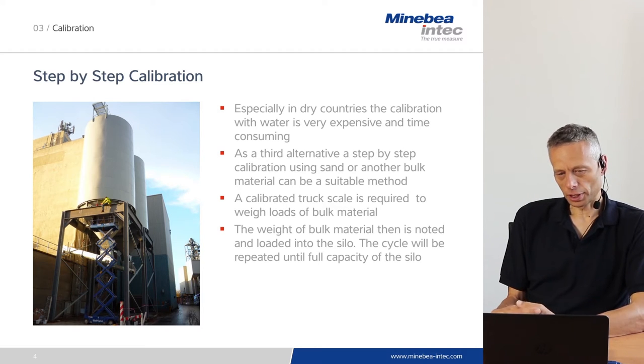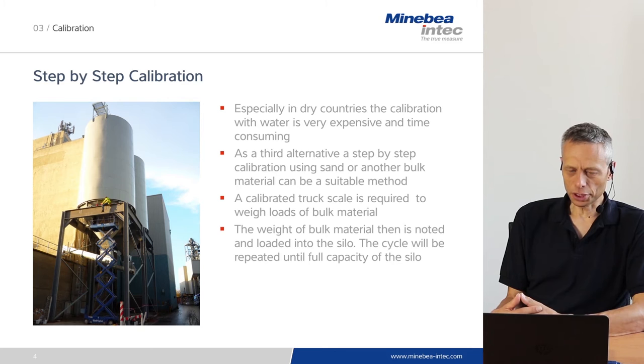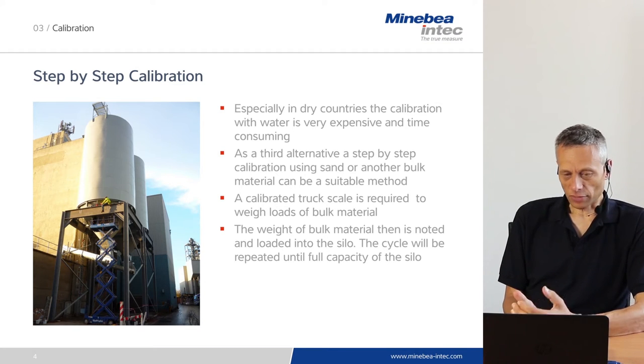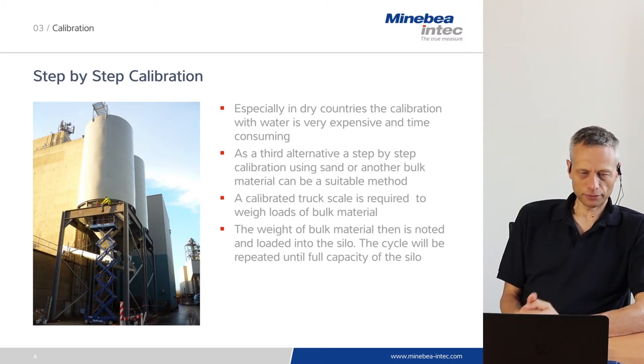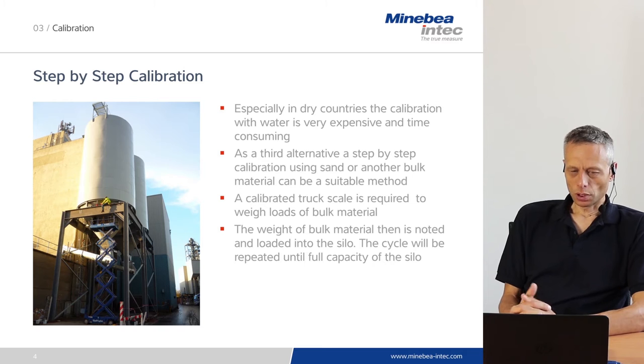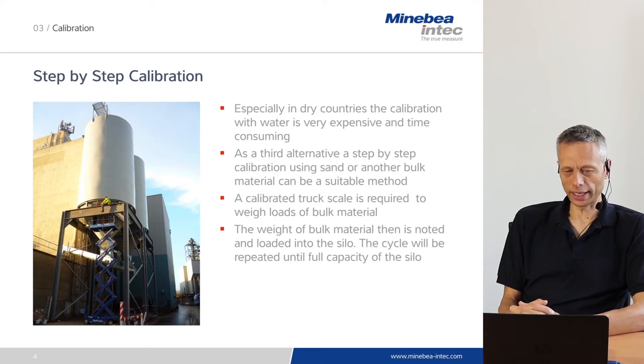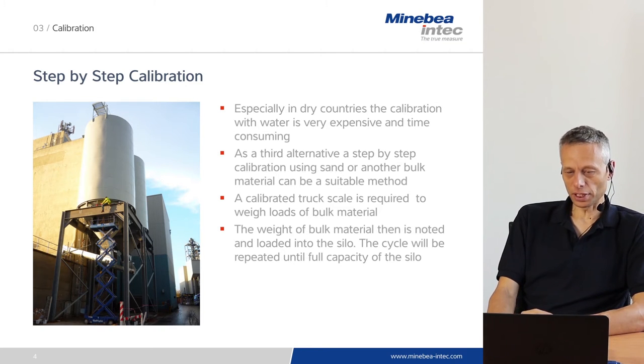Another possibility is the so-called step-by-step calibration. Especially in dry countries, calibration with water is very expensive and time consuming. Step-by-step calibration uses sand or another bulk material — for example, sand or polyethylene granulate filled into silos step by step based on a truck that is loaded and weighed on a truck scale. Large amounts of material can be filled in step by step, and the indicator software allows you to enter the filled-in quantities as a calibration weight. The value is recorded, and then the next amount of material is added so that the weight increases step by step until it reaches full scale. The cycle is repeated until the full capacity of the silo is achieved, though this is also quite time consuming.